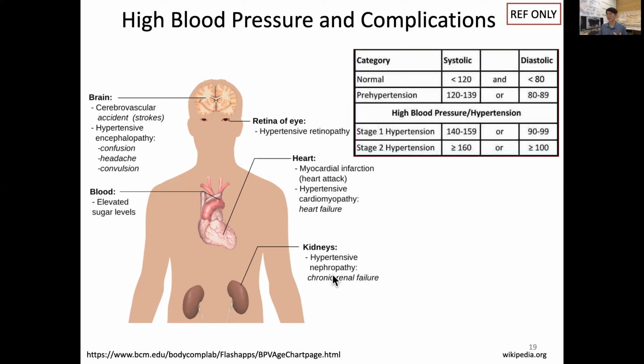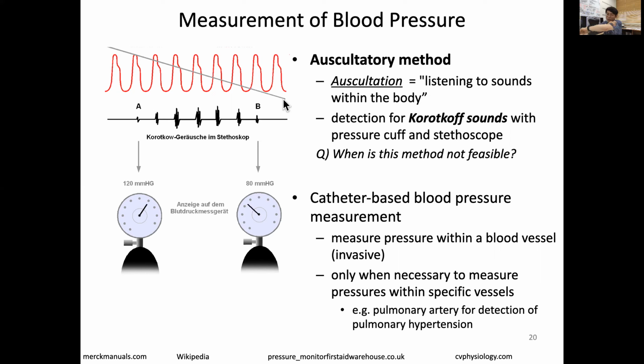Until the cuff pressure is lower than the actual arterial pressure, you don't hear sound, because you're not squeezing the artery anymore and the artery flows smoothly. So by detecting this Korotkoff sound, from the beginning and then later, you can read systolic and diastolic pressure, using a pressure cuff and a stethoscope. This method is not feasible when a patient has an underlying lung problem and you need to check CO2 and oxygen of the blood frequently.